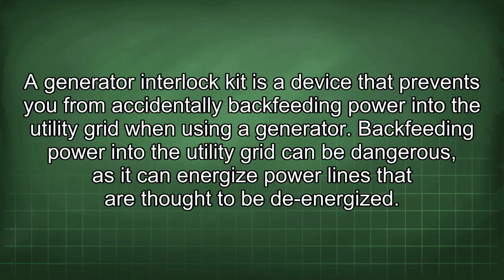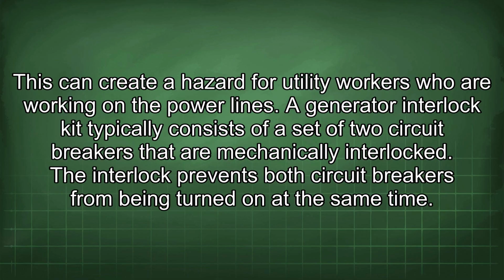A generator interlock kit is a device that prevents you from accidentally backfeeding power into the utility grid when using a generator. Backfeeding power into the utility grid can be dangerous, as it can energize power lines that are thought to be de-energized. This can create a hazard for utility workers who are working on the power lines. A generator interlock kit typically consists of a set of two circuit breakers that are mechanically interlocked. The interlock prevents both circuit breakers from being turned on at the same time.